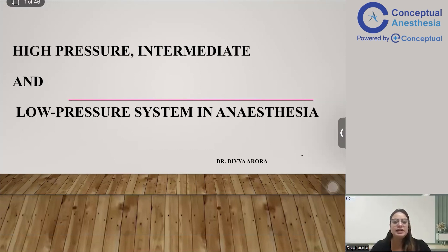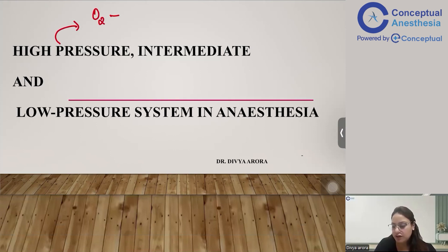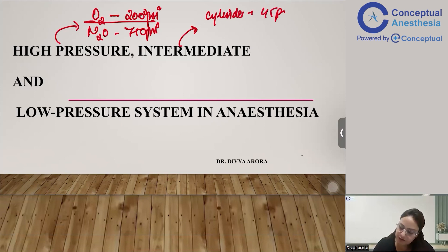We'll be discussing the high pressure system, intermediate, and the low pressure system. When we say high pressure, how high is it? The high pressure system includes oxygen at 2000 psi and nitrous at 750 psi. When we talk about intermediate pressure, for the cylinder it's around 45 psig, and for the pipeline it's around 55 to 60 psig.